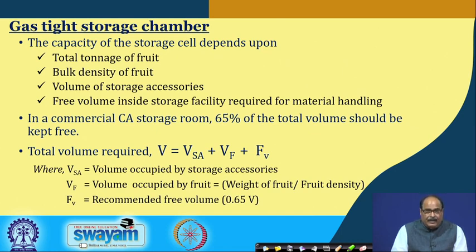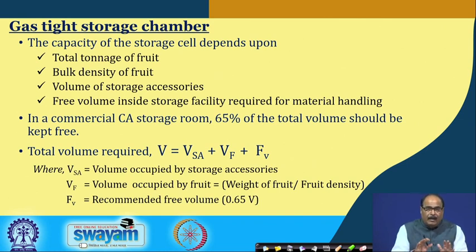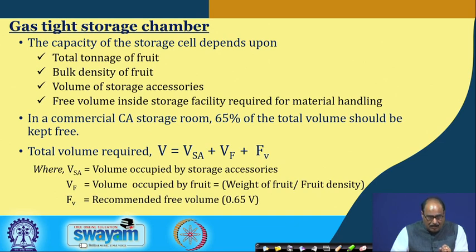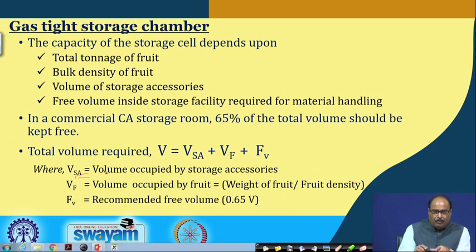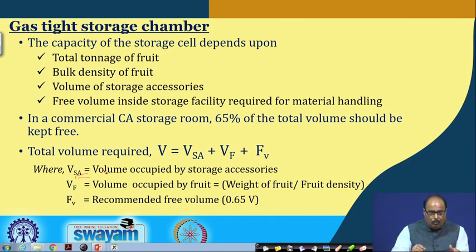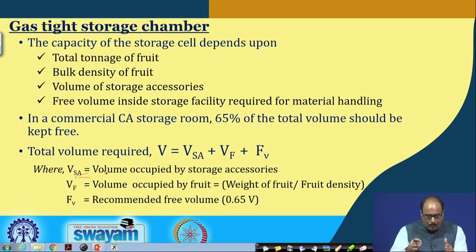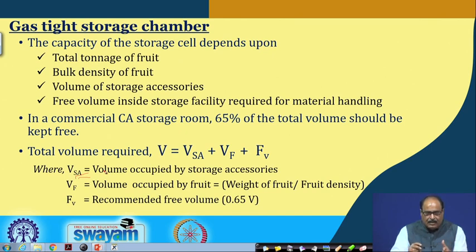As per regulatory requirement, in a commercial control atmosphere storage unit 65 percent of the total volume should be kept free for material movement and other purposes. The total volume of the storage room required can be calculated from the equation: V = VSA + VF + FV, where VSA is the volume occupied by the storage accessories (nitrogen generator, carbon dioxide cylinder accessories, sensors, etc.), VF is the volume occupied by the fruit or food determined by weight divided by density, and FV is the free volume required, which is 0.65V.